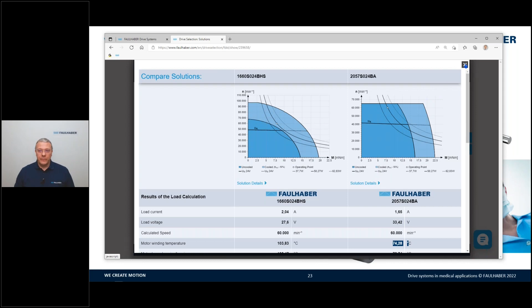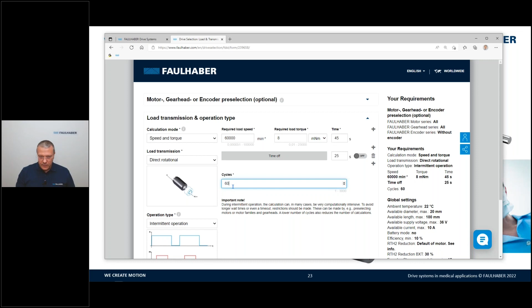For example, here we select intermittent operation, and then we can have this working point for a total time of let's say 45 seconds, with the time off for 25 seconds. Then we have to enter the number of cycles. Why? Because during on-time the temperature of the winding increases, and during off-time it decreases, but with many cycles the overall trend is to increase the temperature. So to reach a stable temperature, let's calculate about 60 cycles and see what happens.